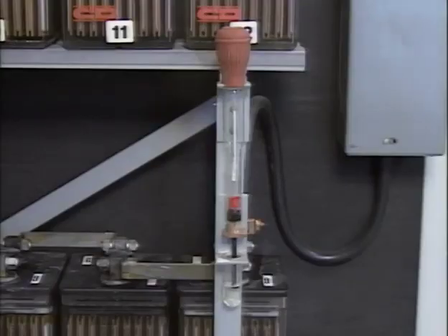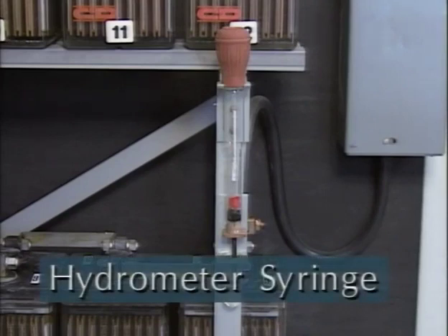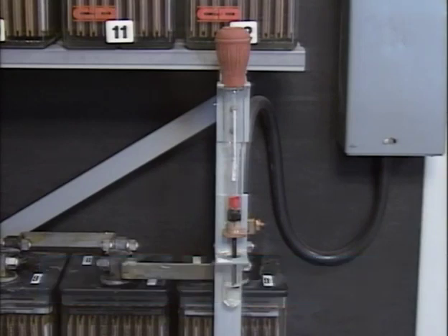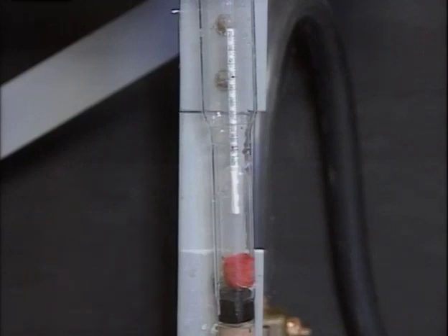Specific gravity is measured using an instrument called a hydrometer syringe. Most hydrometer syringes have the same basic parts. At one end is a rubber nozzle that's inserted into the cell. At the other end is a rubber squeeze bulb for drawing electrolyte into the body of the hydrometer. The body is a glass barrel. Inside the barrel is a weighted float with a graduated scale. The scale markings indicate values of specific gravity. In this example, the scale is marked off in increments of 0.002.